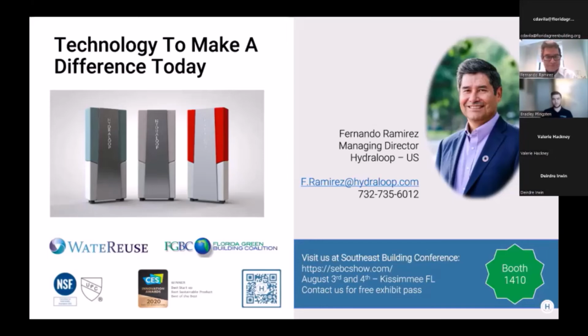Fernando, if there's a power outage or the system stops working, will the areas that use the water be affected? So I can answer that. As far as power goes, the system does have a pump that it uses to distribute the outgoing water. So it does have a 30-minute backup power battery. We do recommend putting a UPS on it. But also, if you do experience a lot of power outages, if it's out for more than a day, you're dealing with hurricanes, you can always set up a bypass loop in those cases. But it does have backups for that.